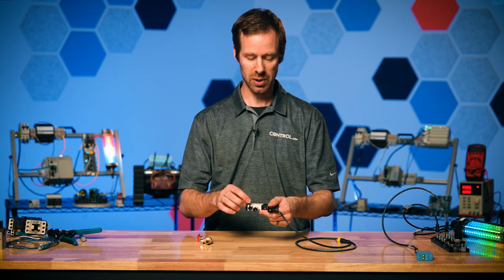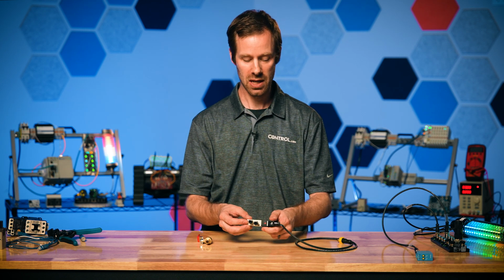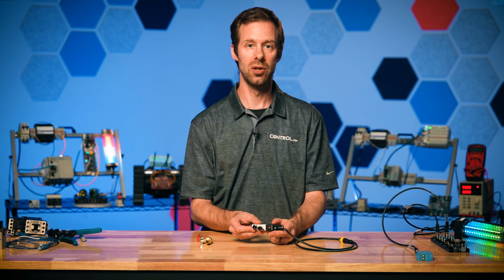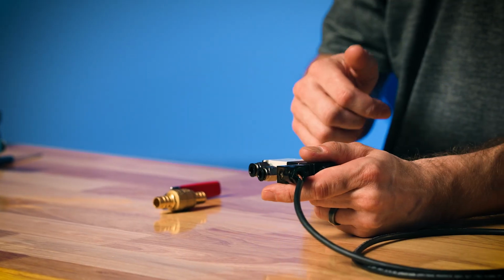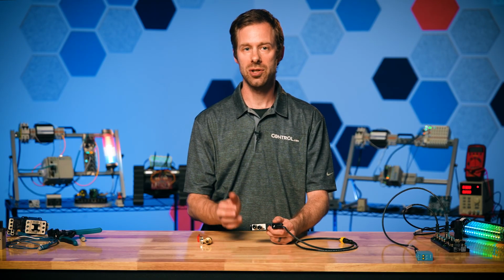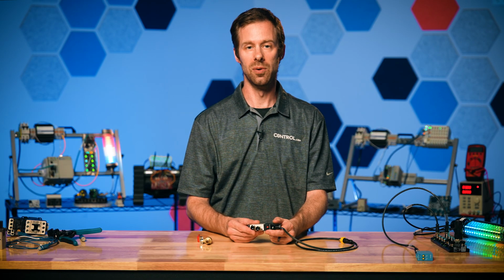Now on the other hand, an industrial valve with a spool inside has passageways that force the fluid, air, to move all over the place inside. Because it requires a lot of energy to force the air through all of these passageways, we lose a lot of energy. And that energy conversion happens in the form of heat and noise, and therefore requires more pressure from our source to force the air through, compensating for this pressure loss, to be sure that we have enough pressure left at the end to drive our load devices like our cylinders and air motors and things like that.